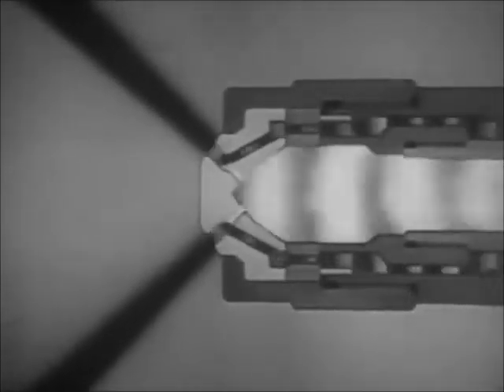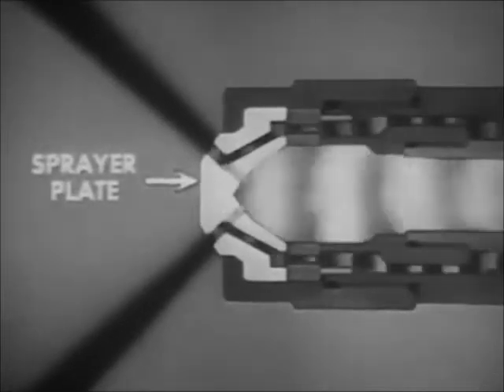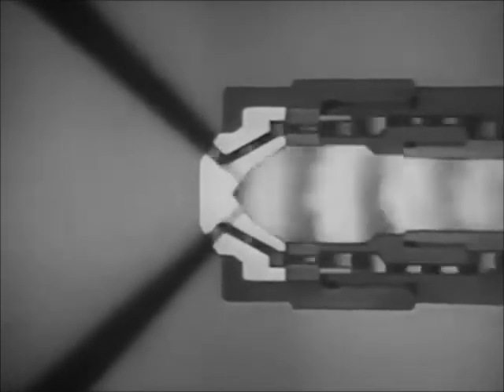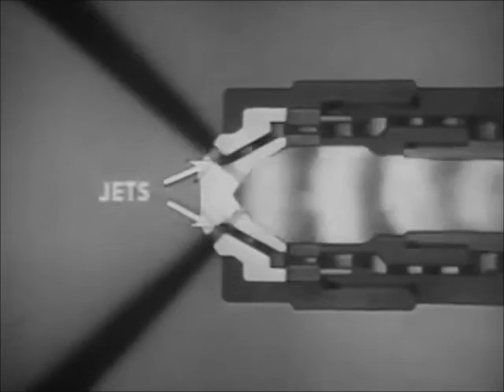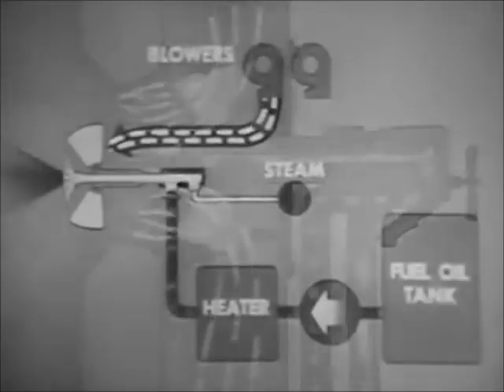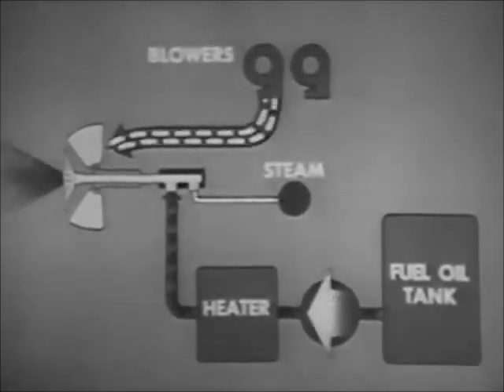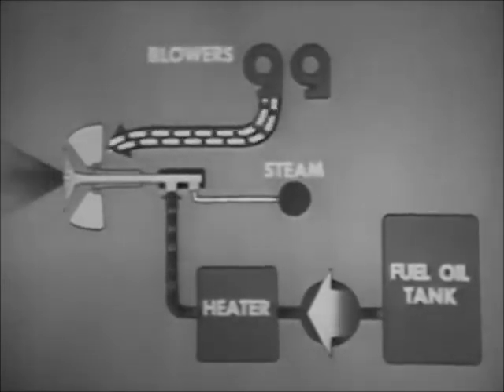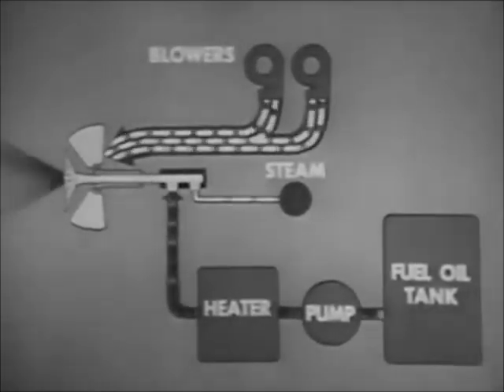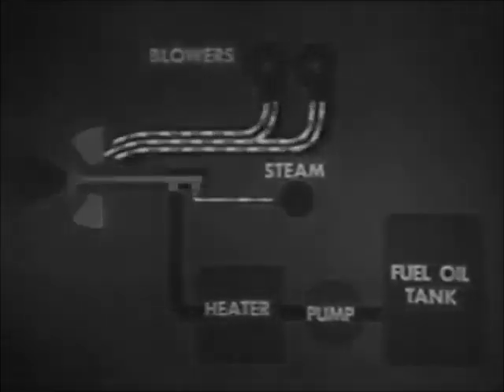In the steam atomizer, oil under low pressure is heated by the steam passing through the barrel and is atomized at the sprayer plate. The register gives the air from the blower a rotating motion and mixes the air with the oil. You regulate oil pressure to control the oil supply and vary steam pressure with oil pressure. You vary the speed and number of blowers to control the air supply.